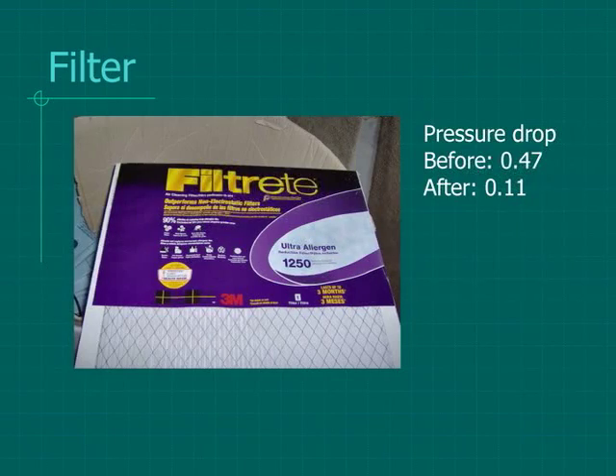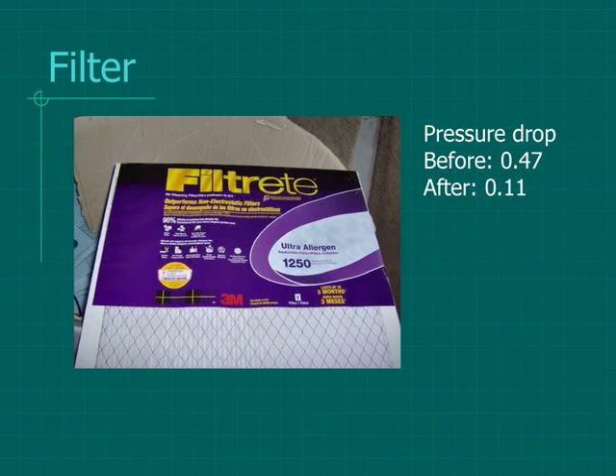We've had this in a house. Pressure drop across the filter, 0.47. That's huge. The pressure drop across the whole system, the return ductwork, the filter, through the furnace heat exchanger, through the air conditioner coil, and then back out to the supplies, should be below 0.5. Just one item in that chain is almost 0.5 already. The after is just a standard filter. That pressure drop was 0.11.